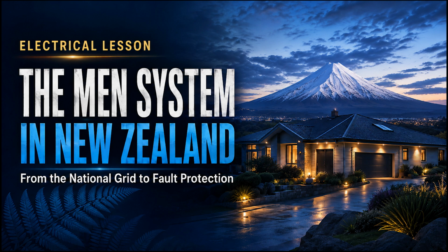Question 2. Where does the neutral originate? At the star point of the transformer's low voltage secondary windings. Question 3. Why is the system called multiple earthed neutral? Because the distribution neutral is connected to Earth at the source and at multiple other points, including connected installations. Question 4. Where is the MEN link normally located? At the main switchboard, between the main neutral bar and the main earthing bar.